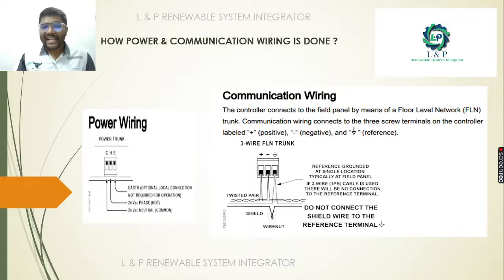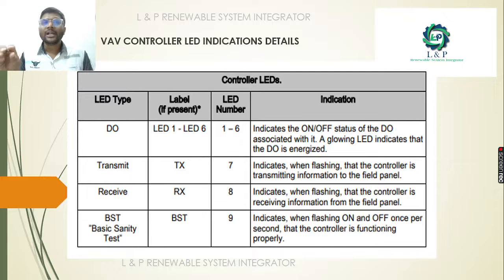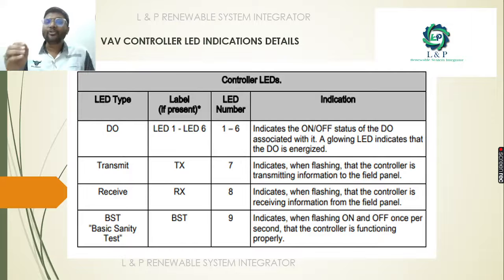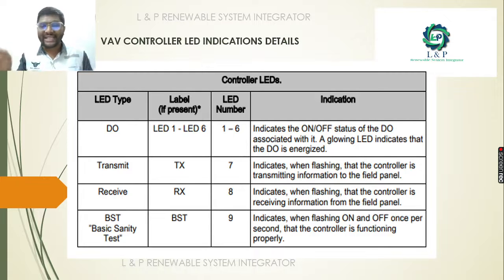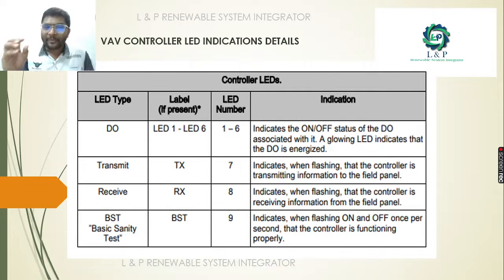This is the in-depth detail about the power wiring. In the HOT terminal we connect the phase and in the COMMON terminal we connect the neutral. For communication, plus and minus have separate terminals. For LED indications: if a digital output is energized, the concerned LED will glow; if the controller is transmitting a signal to field devices, the TX LED will glow; if receiving information from the field, the RX LED will glow. For a basic sanity test — whether the controller is live or functioning properly — there is a continuously flashing LED, like a heartbeat signal, indicating the controller is working.